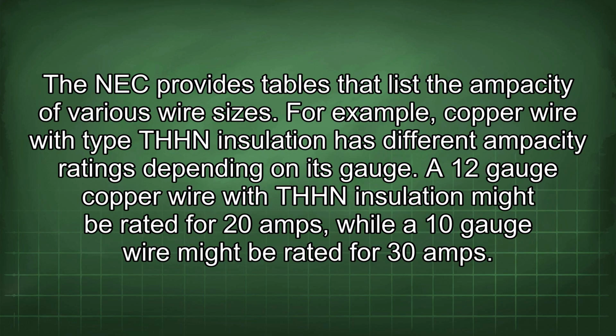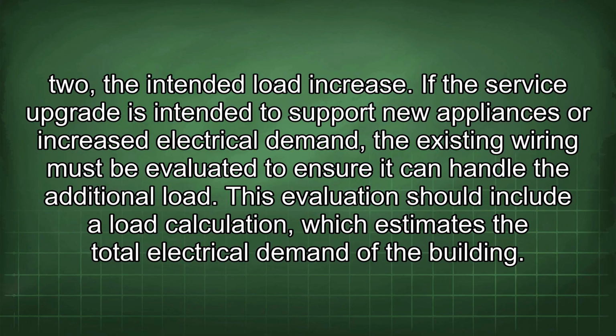The NEC provides tables that list the ampacity of various wire sizes. For example, copper wire with type THHN insulation has different ampacity ratings depending on its gauge. A 12-gauge copper wire with THHN insulation might be rated for 20 amps, while a 10-gauge wire might be rated for 30 amps. 2. The intended load increase.